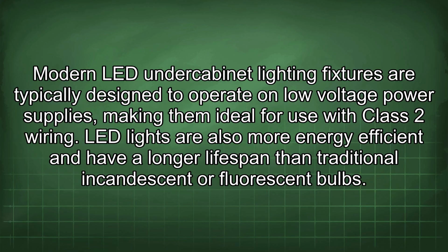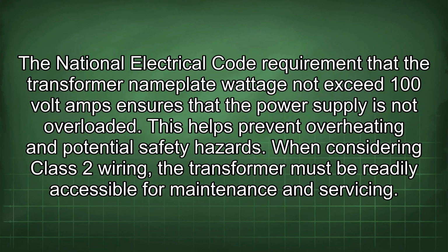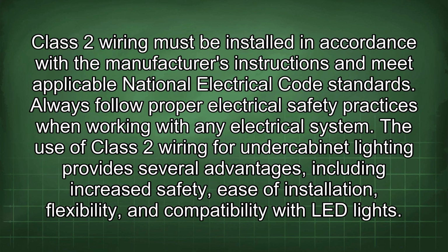LED lights are also more energy efficient and have a longer lifespan than traditional incandescent or fluorescent bulbs. The National Electrical Code requirement that the transformer nameplate wattage not exceed 100 volt amps ensures that the power supply is not overloaded. This helps prevent overheating and potential safety hazards. When considering Class 2 wiring, the transformer must be readily accessible for maintenance and servicing. Class 2 wiring must be installed in accordance with the manufacturer's instructions and meet applicable National Electrical Code standards. Always follow proper electrical safety practices when working with any electrical system.